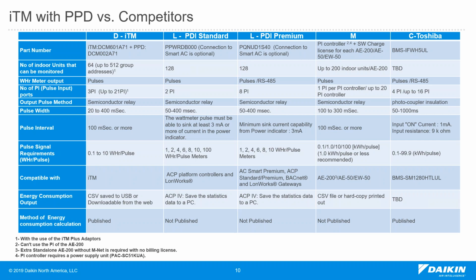If you look into the pulse widths, sometimes in those projects, people complain about, hey, we use that energy meter, it's not working correctly, and what should we do, and we tell them, hey, you guys didn't use the correct meter, and we send out an engineering note about how the PPD function works and what the recommended energy meters are, and definitely that should be used before starting to design the project and look into which meter to select and all of these details. But on the other hand, if you look into other competitors, most of them have the same requirements regarding the pulse details. So the pulse width, pulse interval, and the pulse signal, LG and Mitsubishi, they almost have similar requirements.